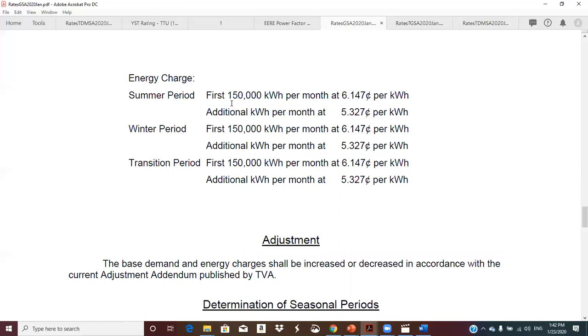So straight multiplication - let's say, did I bring my calculator? We said 1,500 for demand, so peak is 1,500 or so. In a month there's 730 hours on average, times 730, times a load factor, say 0.7, so let's say 750,000 kilowatt hours would be typical for a 1,500 kW demand. So we'd take 150,000 times 0.06147, and that's $9,220.50.